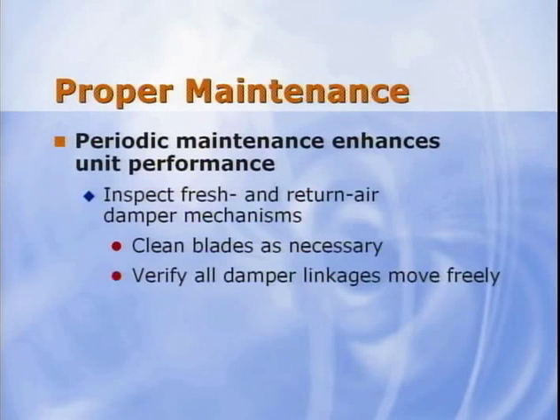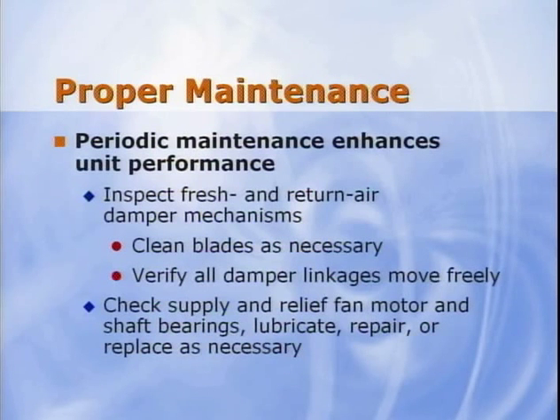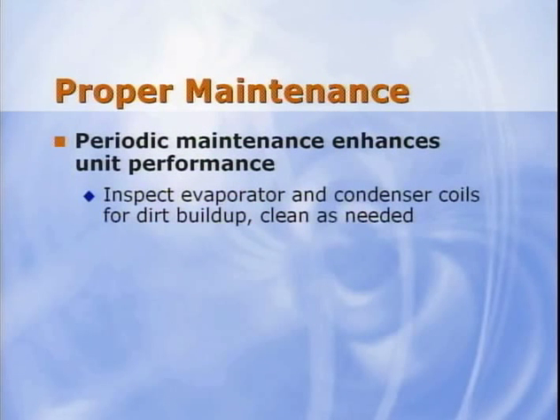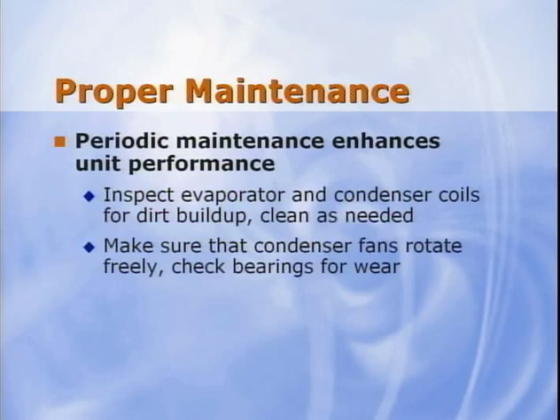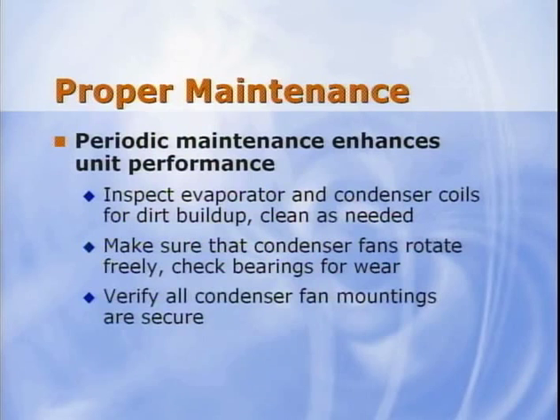This is just good practice. Inspect fresh air and return air damper mechanisms. Clean the blades as necessary. Damaged or loose damper linkage can cause excessive air leakage. You could be wasting energy by unnecessarily conditioning excess fresh air. Check supply relief motor and fan shaft bearings. Lubricate, repair, or replace as necessary. Inspect the evaporator and condenser coils for dirt buildup. Restrictions on either coil increases pressure drop and motor kW. Clean the coils as necessary. Check condenser fan rotation for free movement. Check the bearings for wear. Verify that all fan mountings are secure.